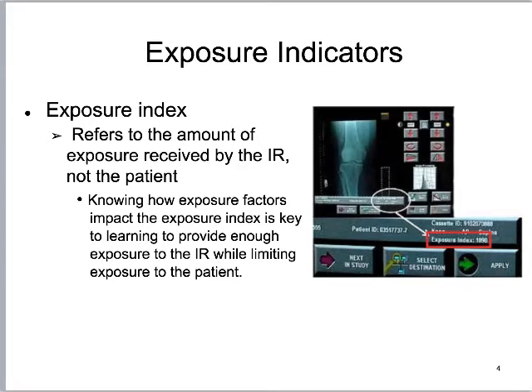Unfortunately, these are confusing as hell. Ideally, what an exposure index refers to is the amount of exposure received by the image receptor — not by the patient. It's not a dose, but it tells us how much exposure traveled through the patient, and the remnant beam struck the image receptor. Knowing this gives me a ton of information: was this technique appropriate? Is this a technique I could use on someone else? Was there an opportunity to reduce dose? This is just an example of where that exposure indicator is buried on an older Fuji system.